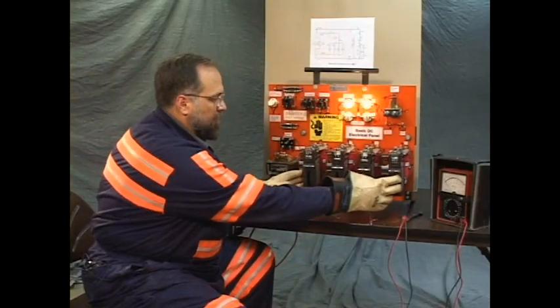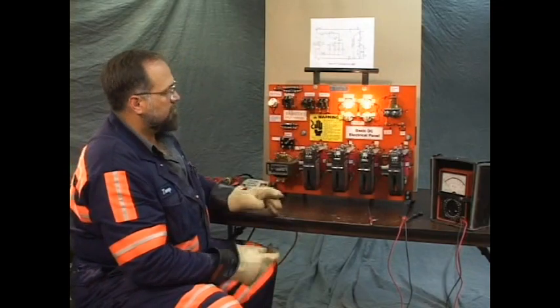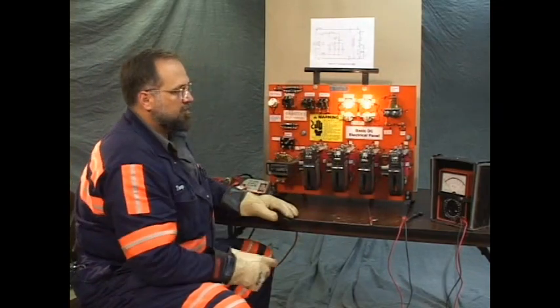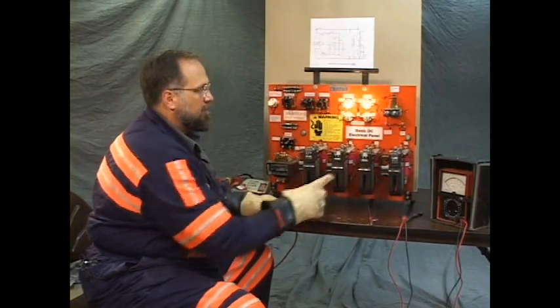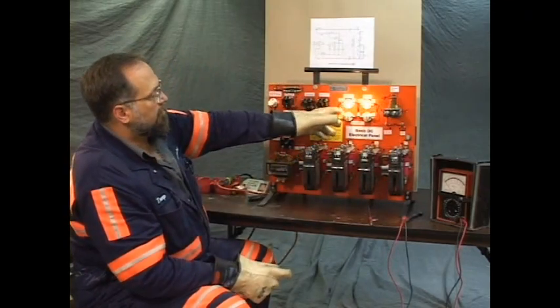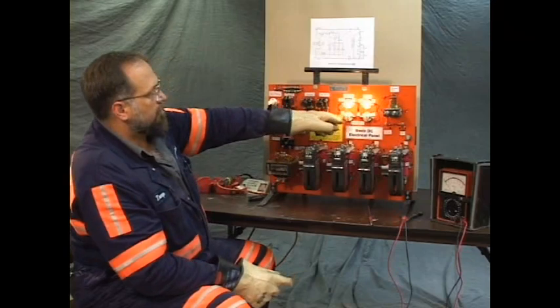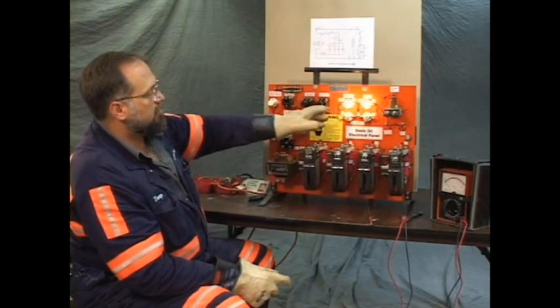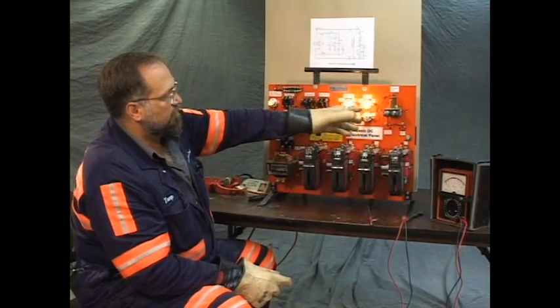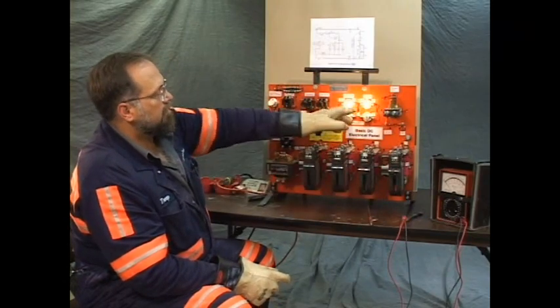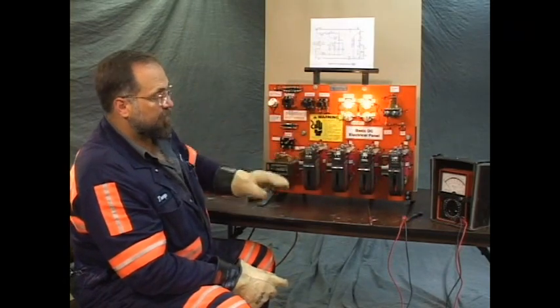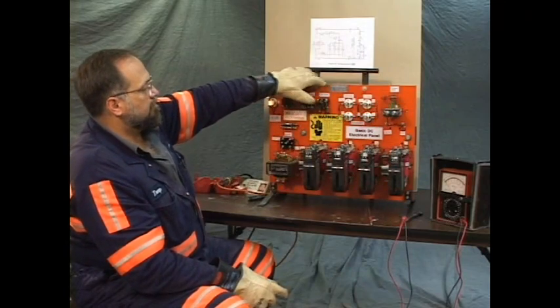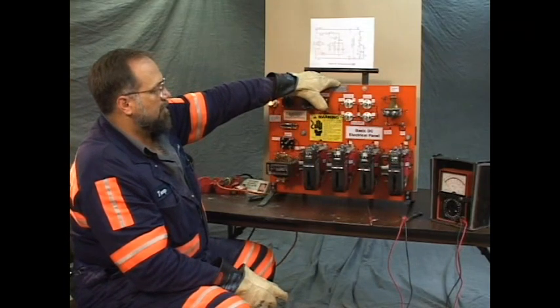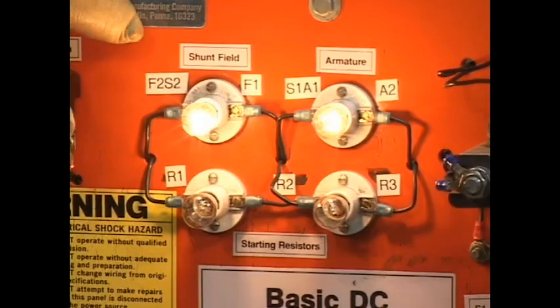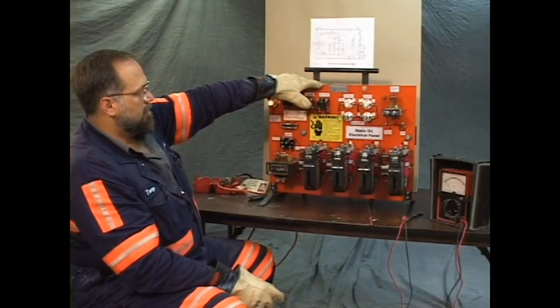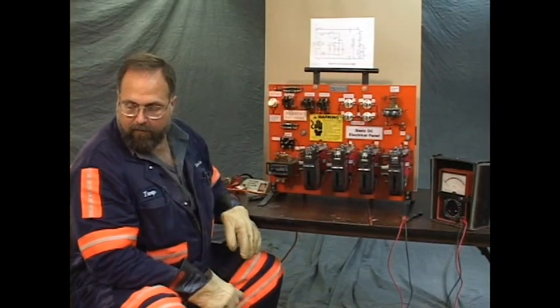You had the M1 and M2 closing simultaneously. After 1 second, 1A closes. After another second, 2A closes. The shunt field light very bright. All 3 of the others dim. When 1A closes, this light goes off. These 2 are brighter. When 2A closes, this light goes off. The armature is very bright. One more time. Watch this closely. Watch the lights. Okay. Now we're going to toggle the problem in, problem number 11.